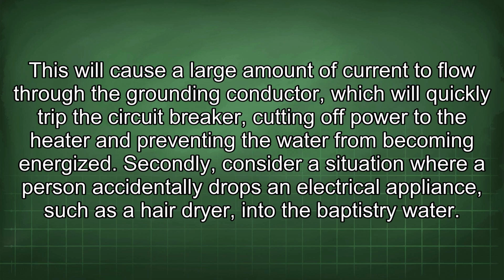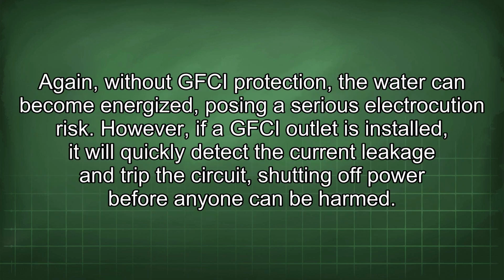Secondly, consider a situation where a person accidentally drops an electrical appliance, such as a hairdryer, into the baptistry water. Again, without GFCI protection, the water can become energized, posing a serious electrocution risk. However, if a GFCI outlet is installed, it will quickly detect the current leakage and trip the circuit, shutting off power before anyone can be harmed.